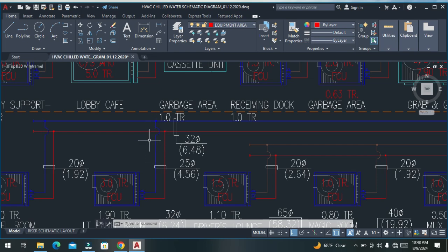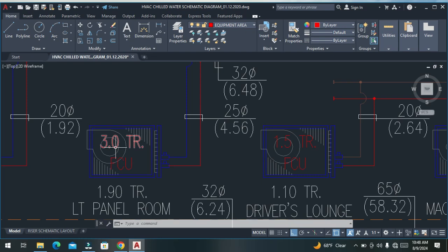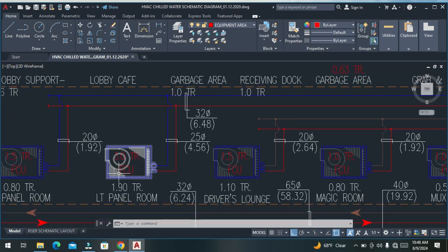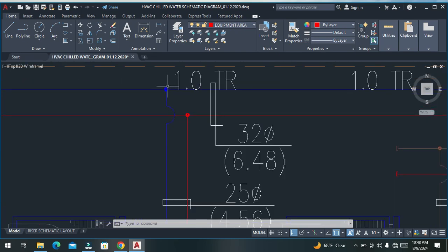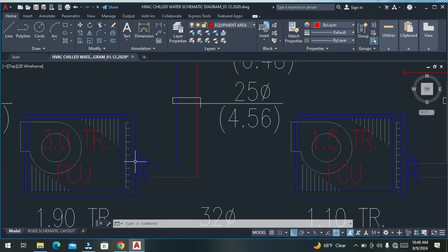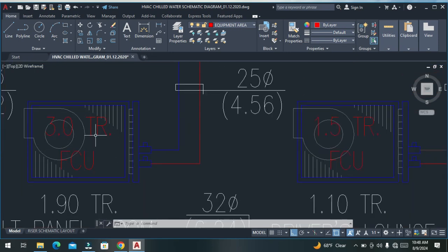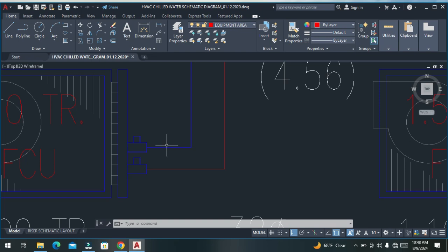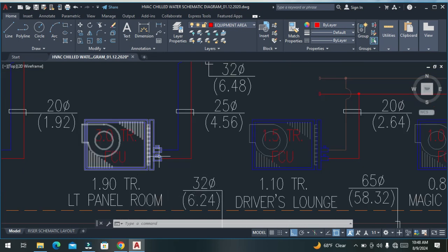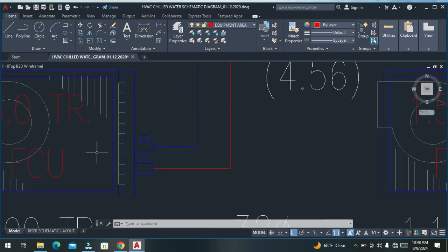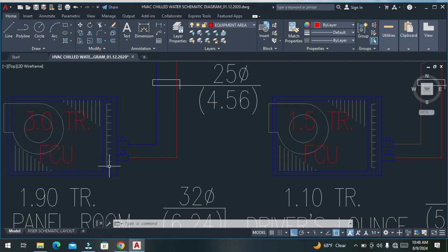Over here we have 1 unit, a 3 ton FCU, fan coil unit. From here again we can take branches, and over here this goes to the supply coil of this 3 ton FCU unit. So this is actually the cooling coil supply, and from this we trace 1 unit, so it will be clear to us. This is the chilled water supply, and this again is the return line of this FCU. Water enters from here, then it leaves from here, from the coil.